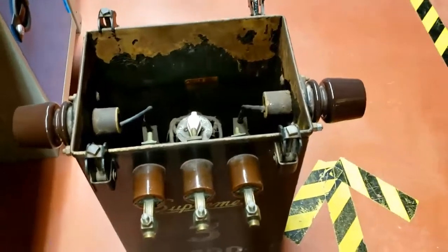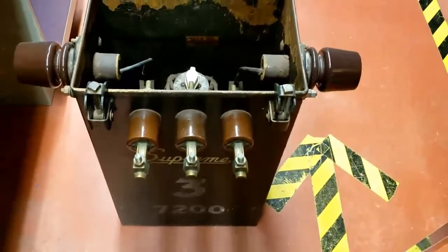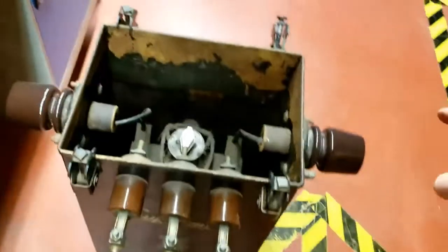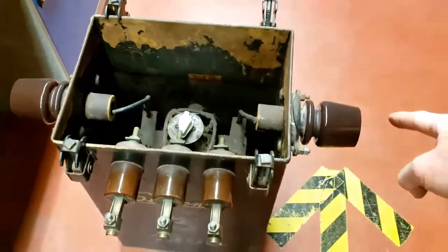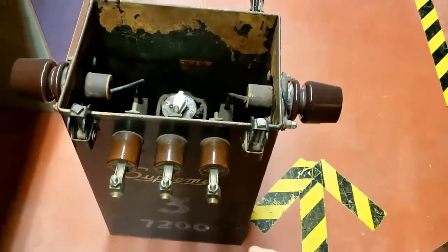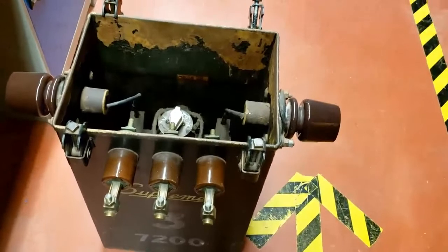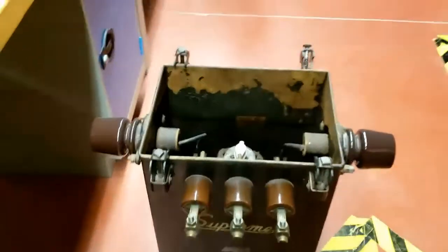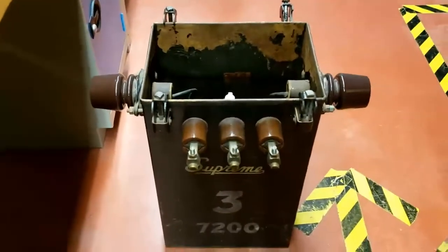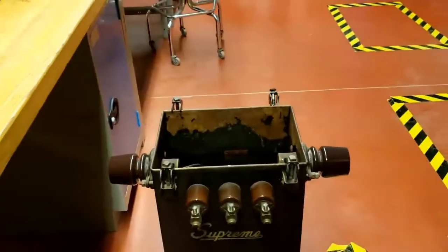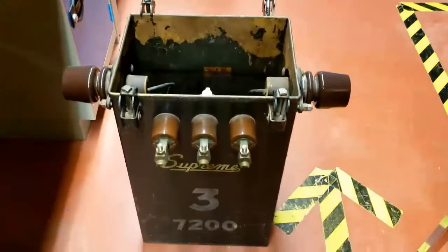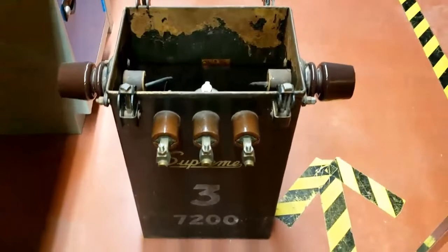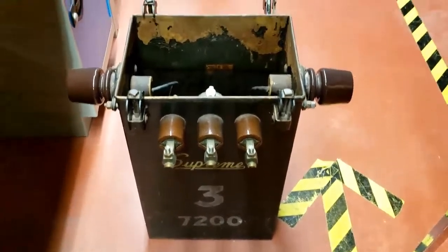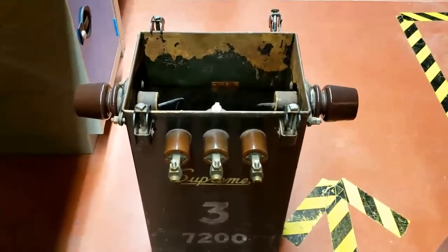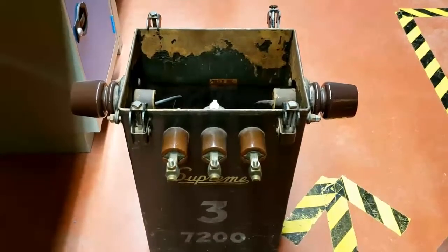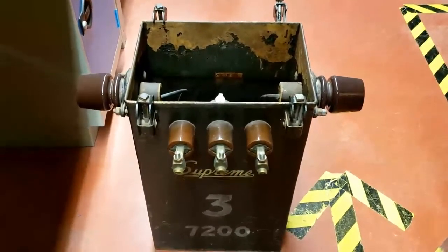Then you're going to use the Megger, and you're going to Megger out high voltage to low, high voltage to ground, and then low to ground. And that will test the insulation. And then you're going to reverse the connections, because what happens is you get a bit of a capacitive charge built up. And you'll see what happens when you flip your leads and measure it in reverse.